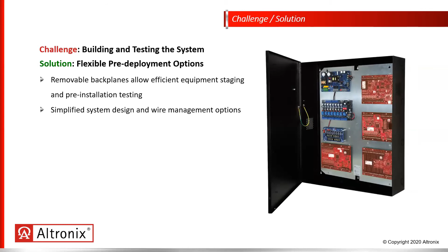So because the backplane is removable, in a larger deployment, we have the ability to deploy the enclosures out to the job site, maybe have the electrician hang the enclosure, pipe to it. In our shop now, we can lay out the backplane, we can mount our access controllers, Altronix power supply subassemblies, handle the inner wiring there. And then when it's ready to go, take that backplane to the job site, install it into the enclosure, and land and dress our field wiring.